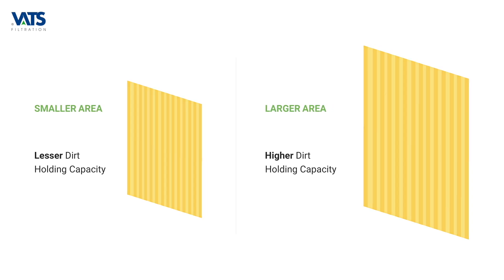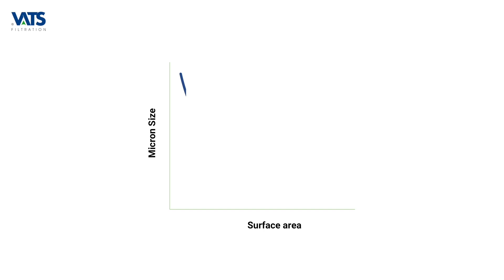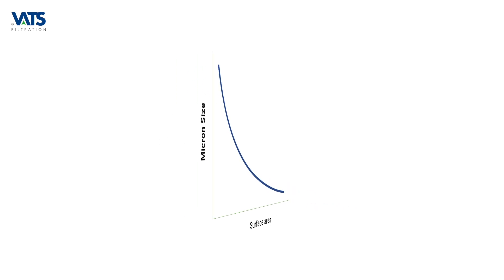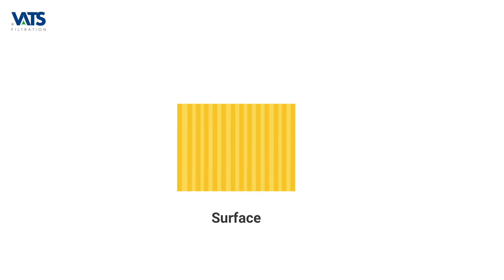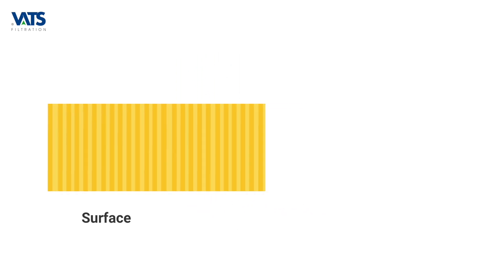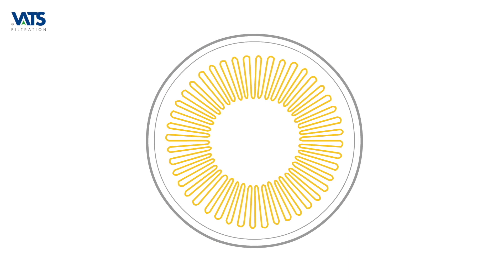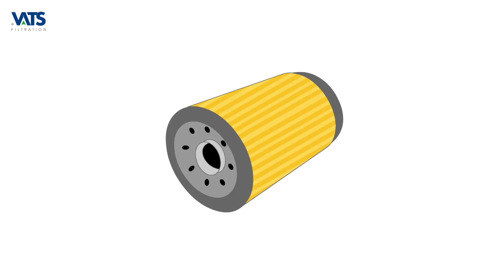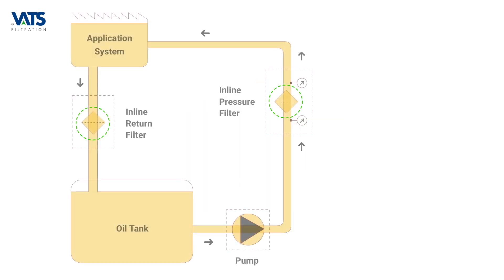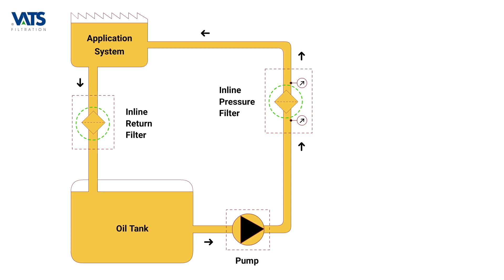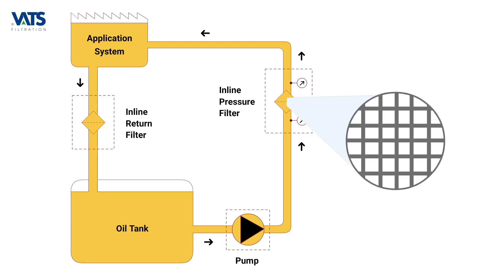The effective dirt holding capacity is thus substantially lower. The dirt holding capacity will be decided by the surface area of the filter — as we lower the micron size of the mesh, larger will be the area required, as it will clog faster. We can increase the dirt holding capacity by increasing the surface area, which is what's done in conventional filters by packing in a lot more of the filter element in a given space.